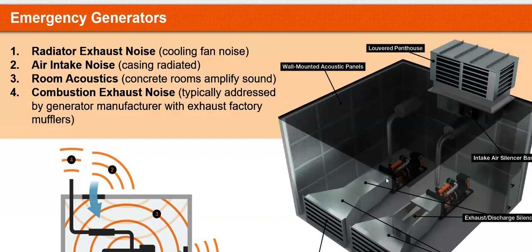The transitions and the connections from the generator to the silencer here, and from the silencer to the louver, that's also double wall. In the scenario where they don't want to use wall mount panels for cost savings, and you're amplifying noise within the room, you don't want all that sound to echo around, get amplified, bypass the silencer, break into thin sheet metal, and then out through the louver, creating issues. So in order to avoid bypassing the discharge silencer, you want to make sure that those transitions are double wall, and you are able to insert your dampers.